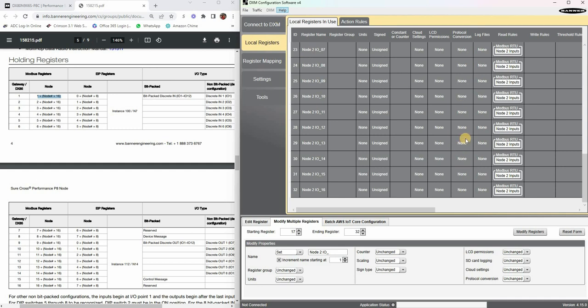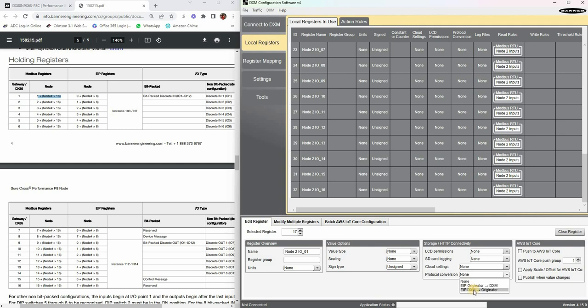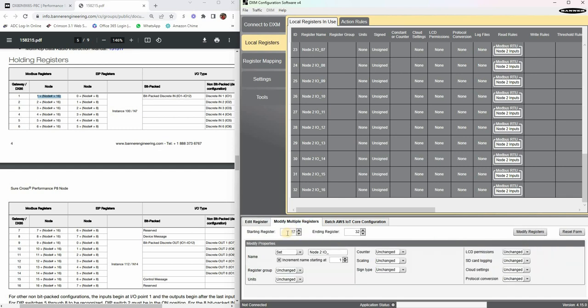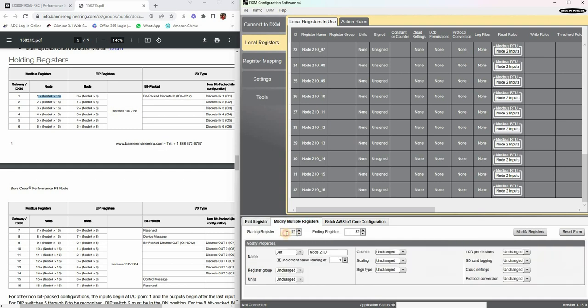If I wanted to make this accessible for Ethernet IP, what I need to do now is go here to my protocol conversion. And since it's all inputs, I want to designate the destination. These are all going to go from DXM to the originator, meaning the PLC. I can make this change for each one of those registers. I just need to allocate the destination here and I have to do that for each local register.